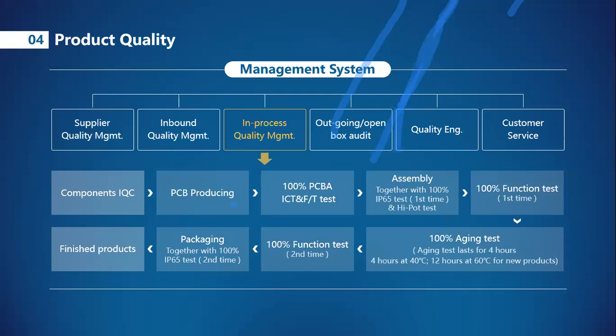When a single product tests okay on all these parameters, it passes the test, and then we perform a 100% aging test twice, in which the product is tested at 40 degrees for 4 hours and at 60 degrees for 12 hours.